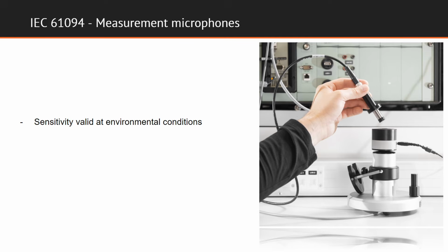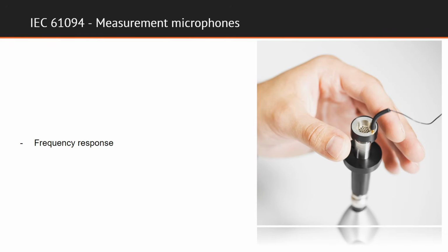The measured sensitivity is valid at the environmental conditions during the measurement. Corrections are of course made for the influence of environmental pressure, temperature, and humidity on the reference microphone. In addition to measuring the sensitivity of the microphones, we also determine the frequency response by using an electrostatic actuator, which can be seen on the picture. This is a widely used tool that can simulate a constant sound pressure on the diaphragm of the microphone over a wide frequency range.